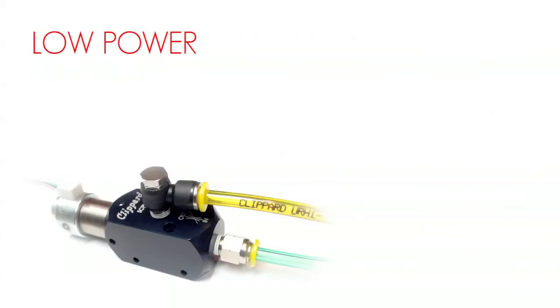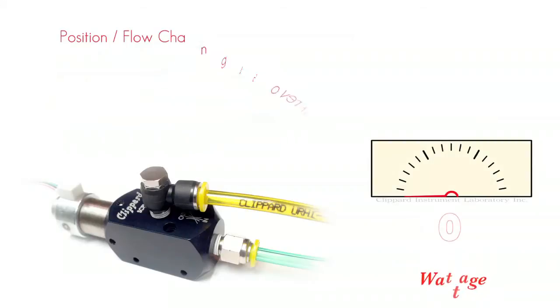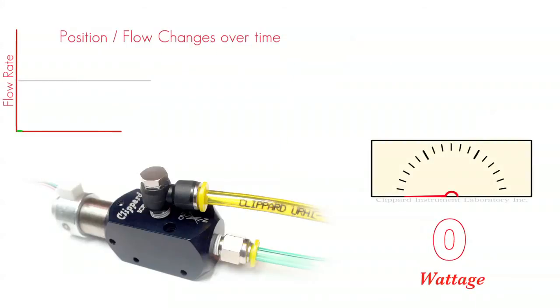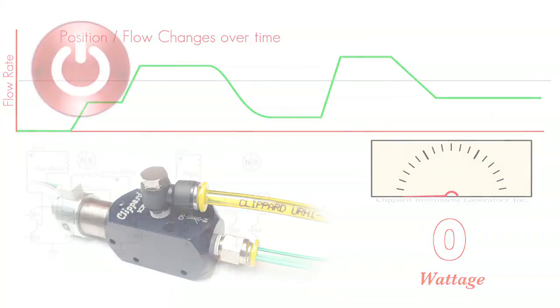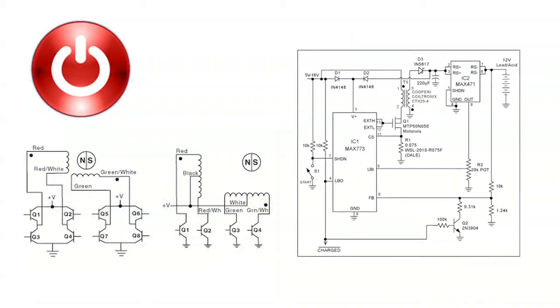Another interesting feature is its low power usage and latching abilities. The valve uses less than 4 watts of power to change position. Just like a needle valve, no power is being used to maintain open, closed, or a flowing position unlike other proportional valves on the market. Fail-safes to close in case of power loss can be built into any controller and even include battery backup.